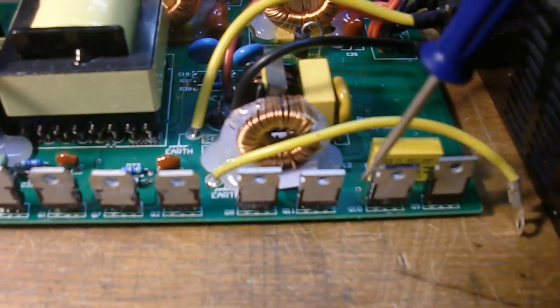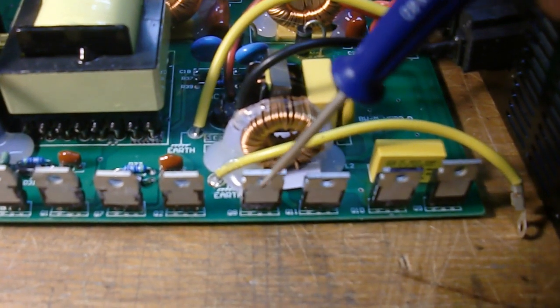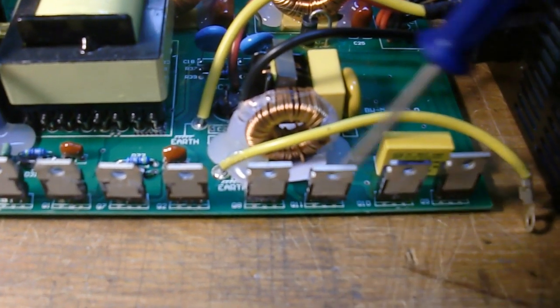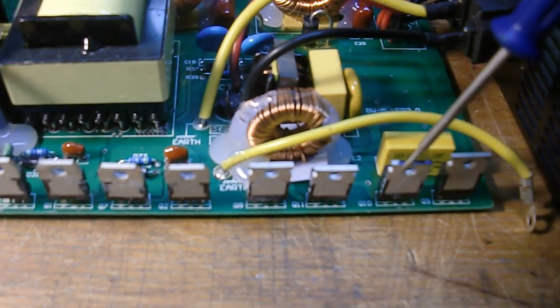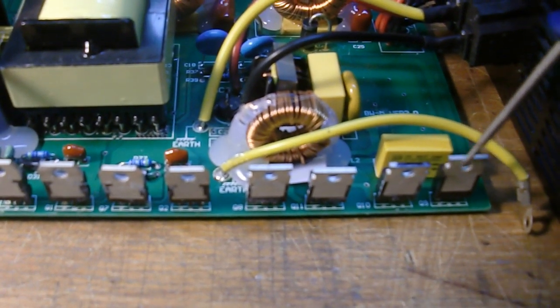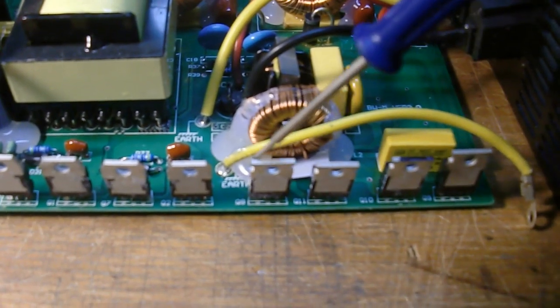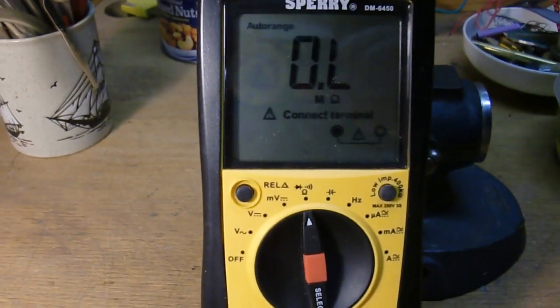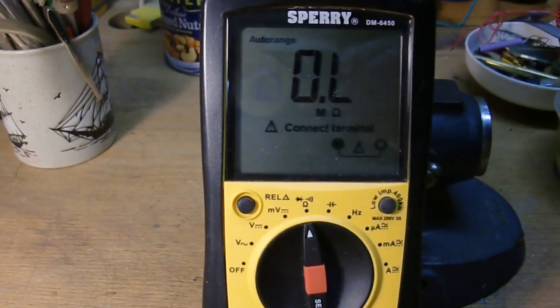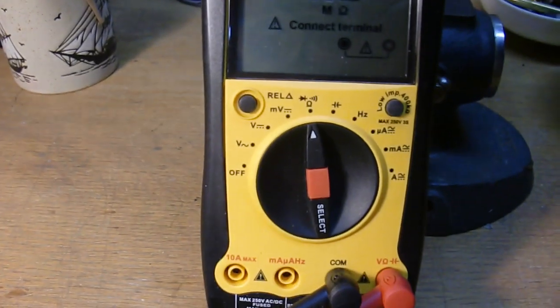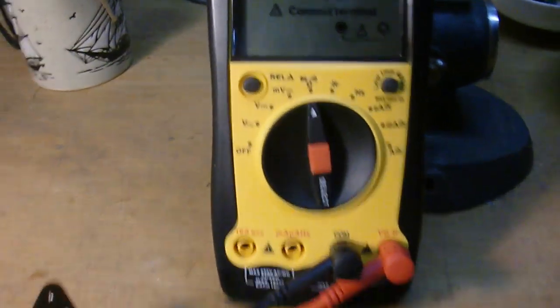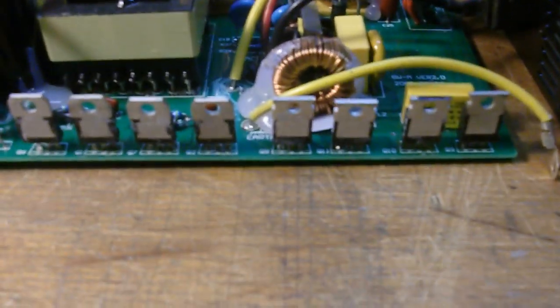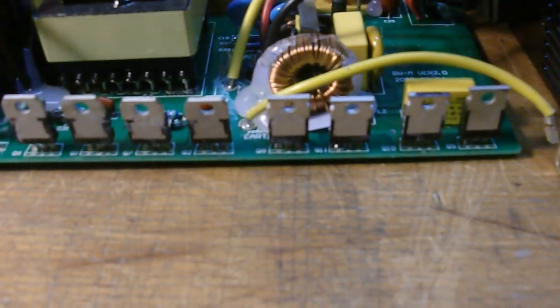Now these are the four AC MOSFETs. And so generally one of these is shorted. And so what you need to do is take your ohmmeter, put it on ohms, and then go and check each one of these individually. And so I'll do that here.